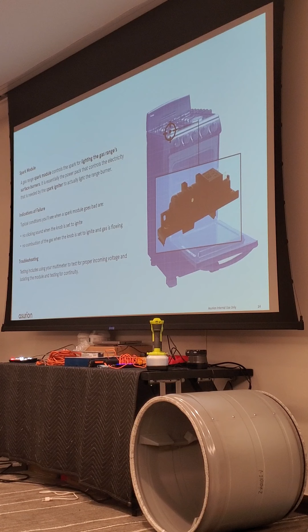The igniter. The igniter is used to open the gas valve once the igniter gets up to amperage. What is the average amperage going into the igniter? 3.3. That's usually about right, about 3.3 amps at full speed, and then obviously if it starts to glow, it's a lower number. As it starts to glow or as it gets up to full power, the amperage actually drops, doesn't it? Okay? Does the igniter on a range ever go out?